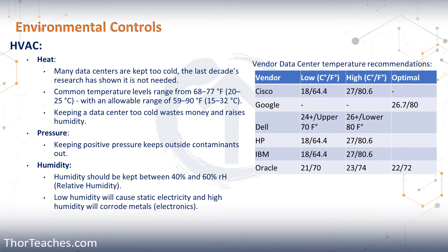Another negative side effect from keeping our data centers too cold is that it raises the humidity level. We have humidity control in our data center, but keeping the temperature lower than it needs to be raises the humidity level, so we also spend more money pulling that humidity out of the room. I have been in major data centers where they kept the temperature around 60 degrees Fahrenheit or just around 15 degrees Celsius — on top of wasting money, it's also miserable to work in. Over the last 5-10 years, it's become more common knowledge that it is okay to save money and raise the temperature. Somewhere in the low 20s Celsius or low 70s Fahrenheit is probably a good range to shoot for.